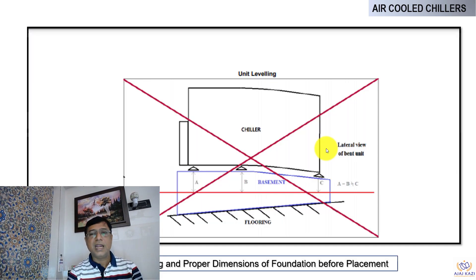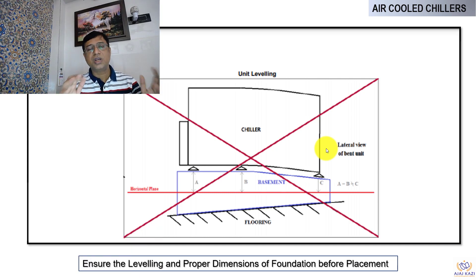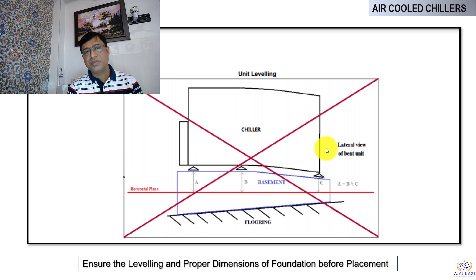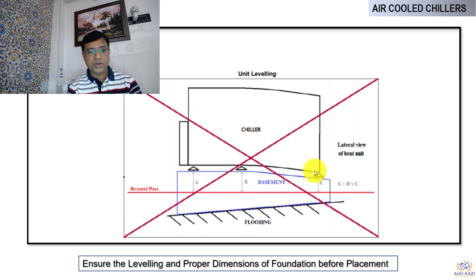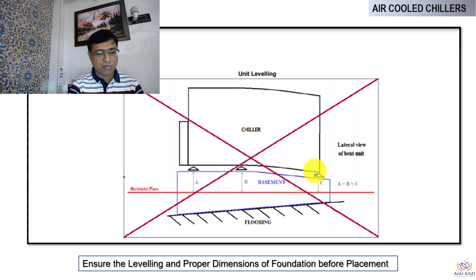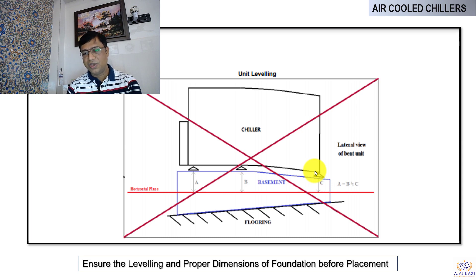An important aspect of chiller installation is that we generally mount them on a foundation, or when placed on top of buildings we create a structure on which the chillers are installed. It is important to ensure the structures are leveled properly so that the units are leveled properly, otherwise we will have issues. We should also ensure the proper dimensions of the chillers match the foundation being created. Most of the time, foundation work is done by civil contractors and when the chiller arrives there is a mismatch of communication — they do not fit on the foundation properly and we lose a lot of time.